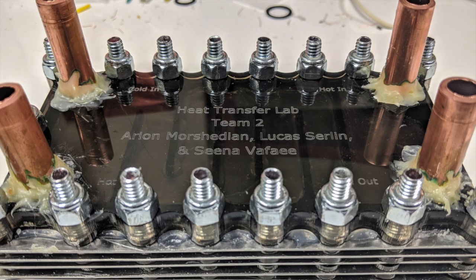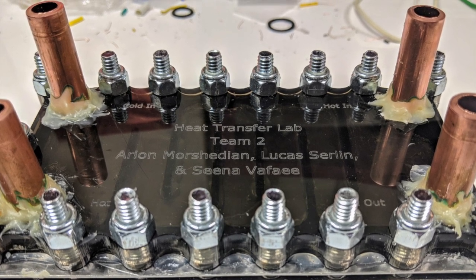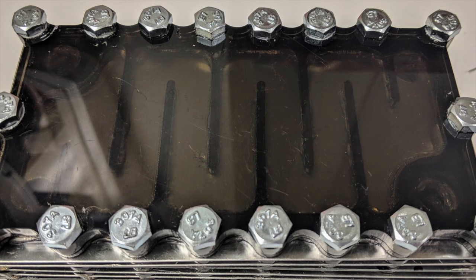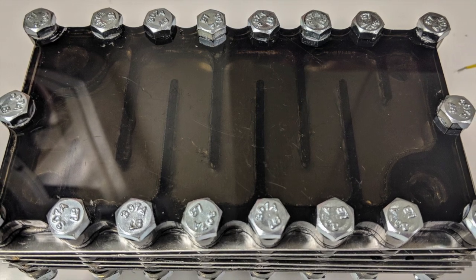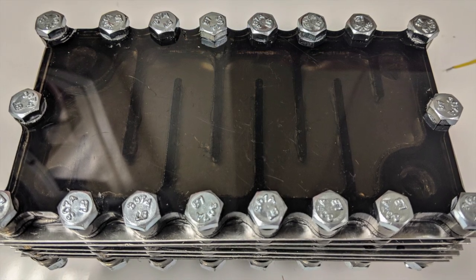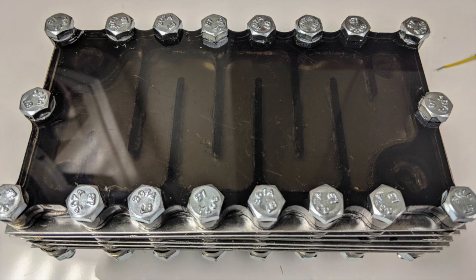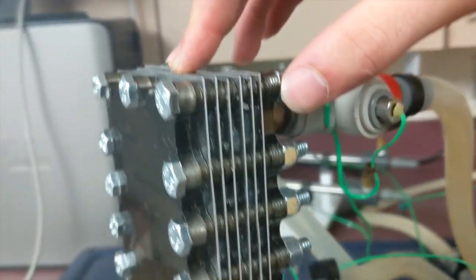There were multiple changes that we made after testing the prototype heat exchanger. There were 2 main goals we had. Number 1 was to reduce the leakage that we saw with the first test, and the second goal was to increase the amount of heat transfer. The leakage was reduced by using better manufacturing processes, so using a proper jig to ensure that the tolerances were a little bit tighter.